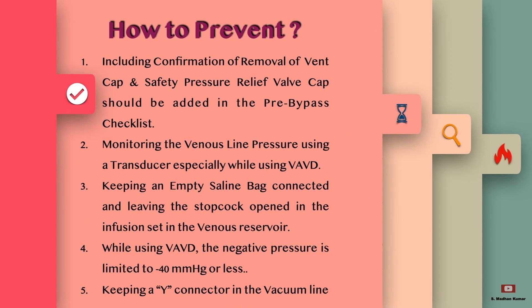How to prevent this: include confirmation of removal of the vent cap and safety pressure relief valve cap in the pre-bypass checklist, and make sure it has been checked and read aloud for all team members. Monitor the venous line pressure using a transducer, especially while you are using a VAVD device.